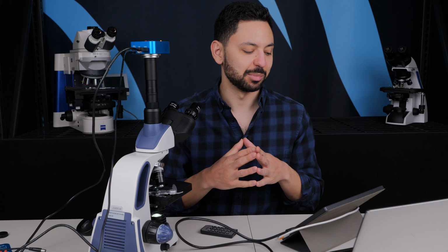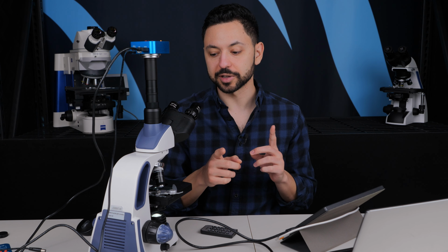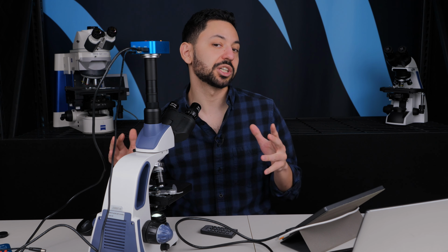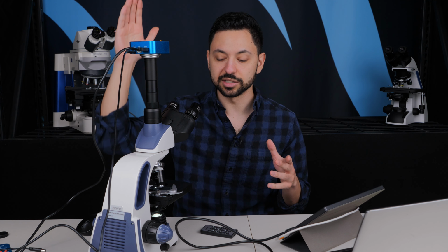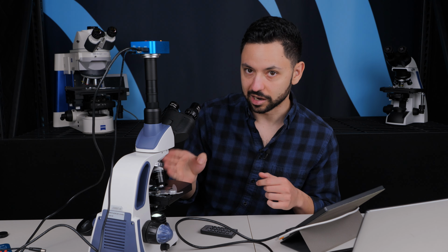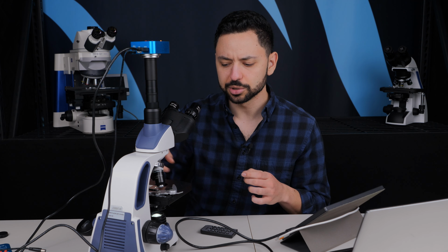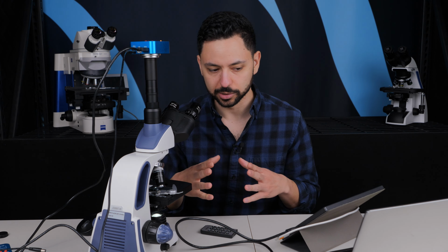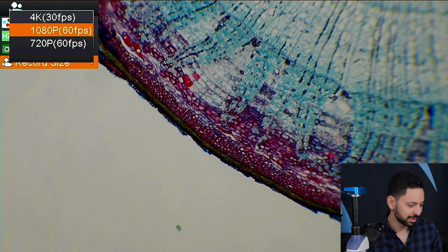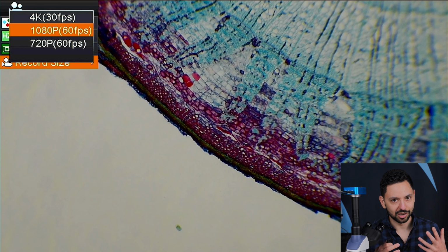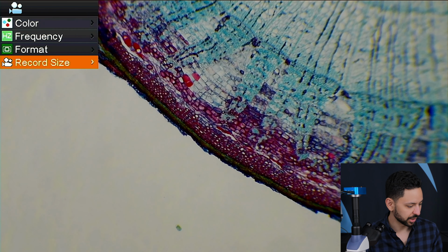I'll go ahead and say it: the 4K images that you get rather than 1080p are not really that different. In fact, you pretty much can't tell a difference. The reason for that is that the video resolution is not the limiting factor in this case. It's almost always the clarity of the optics of the microscope and the image sensor itself, but it's usually the objectives. So honestly, I would just leave it at 1080p. If you want to do 4K, maybe in certain circumstances you'll be able to get better resolution out of that. You're running into limitations of optics at very small scales. So that was record size.